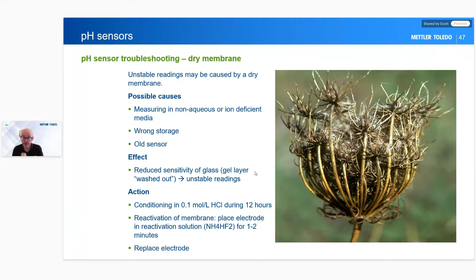And then a reactivation solution can be used, which is a light hydrofluoric acid that sometimes can correct it as well. Obviously, if none of these things work, and it's an old electrode, then the only thing to do is to replace the electrode. So hopefully that's helped you take care of the electrodes, choosing the right buffers and solutions as well.